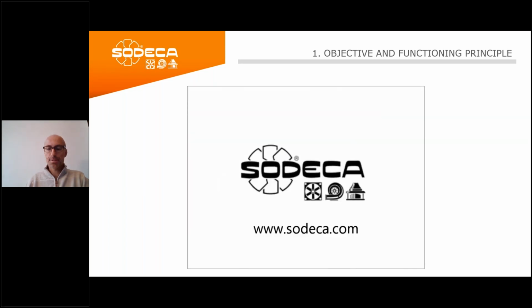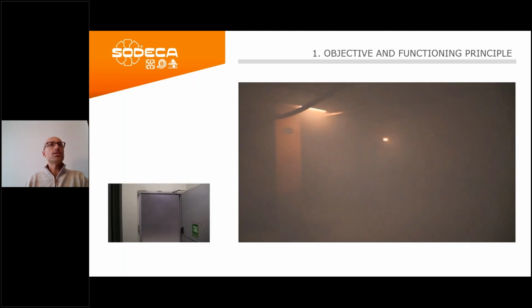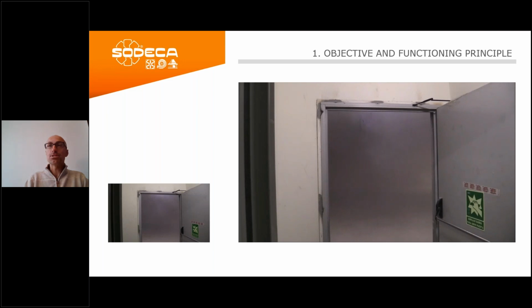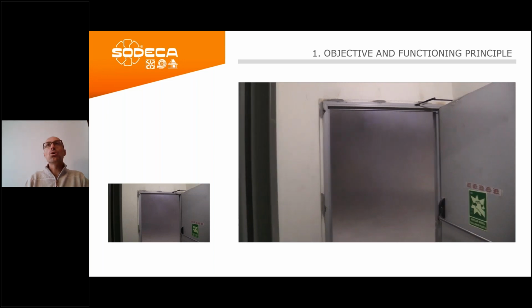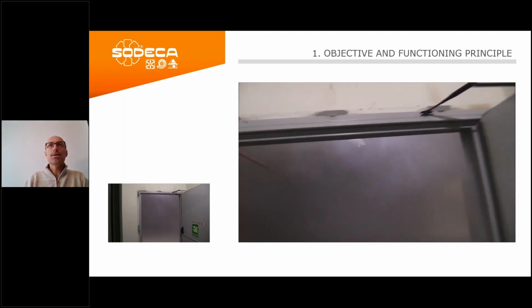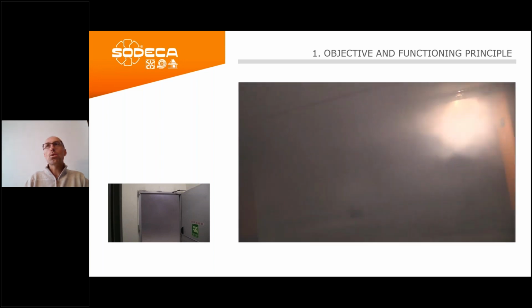In this other video, you can see a smoke test we carried out in a car park. We had this stairwell with a pressurization system installed. So even with the car park filled with smoke, the smoke did not spread into the staircase.